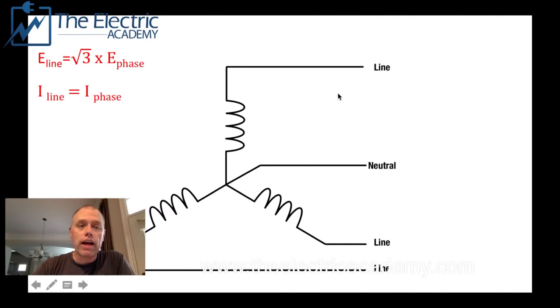And you have less insulation too because this voltage is going to be lower, but you can still get the 208 safely out of that. So it's very useful that way. And you see them a lot on the, if you have a delta Y system, is they use this to get the two voltages out of it. Very common in buildings, commercial and industrial, you'll see that. Some of the disadvantages are if you've got a Y connected motor, you get less torque out of it, and it's a little more expensive. So that's your Y connection.